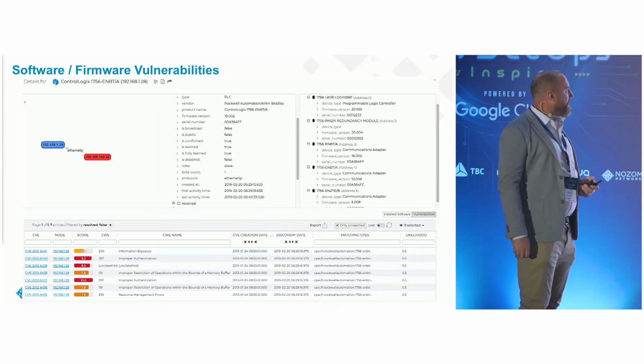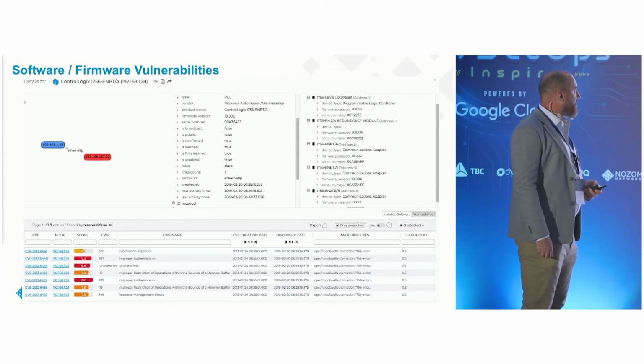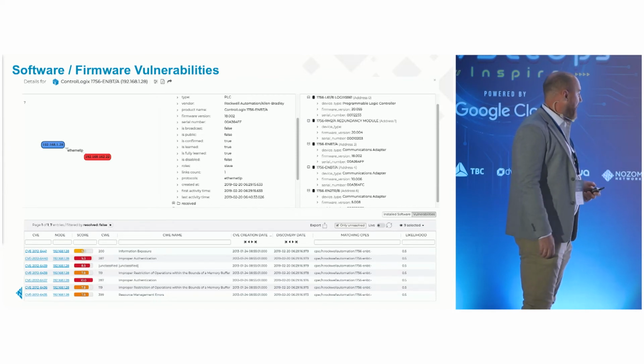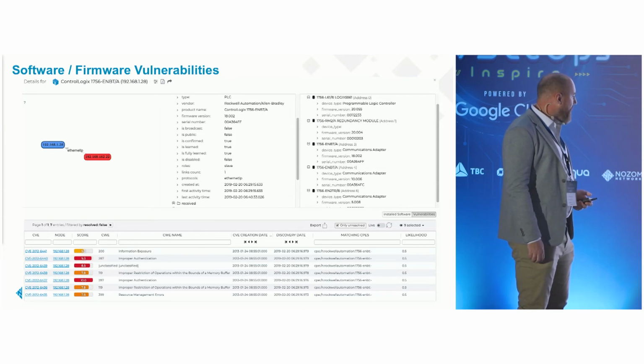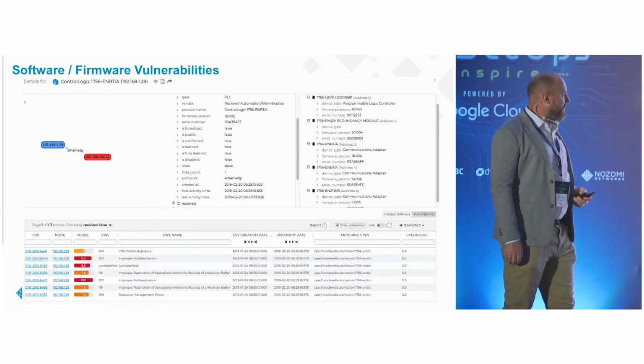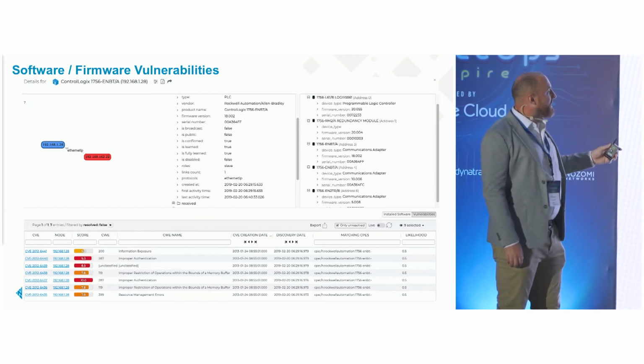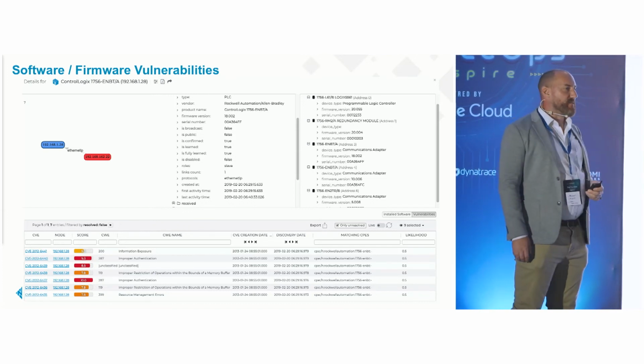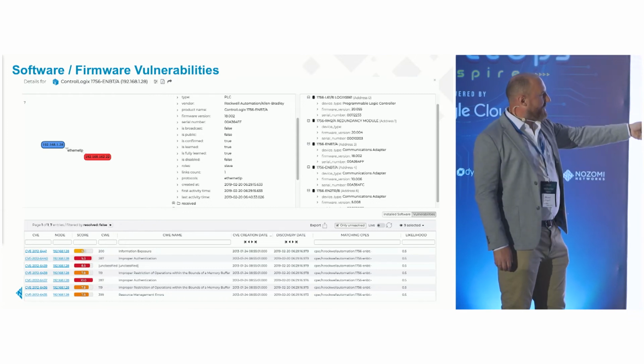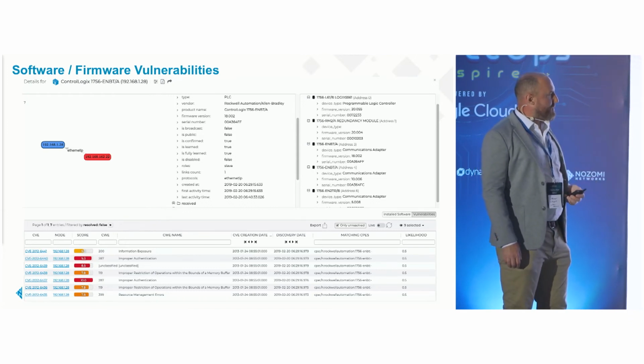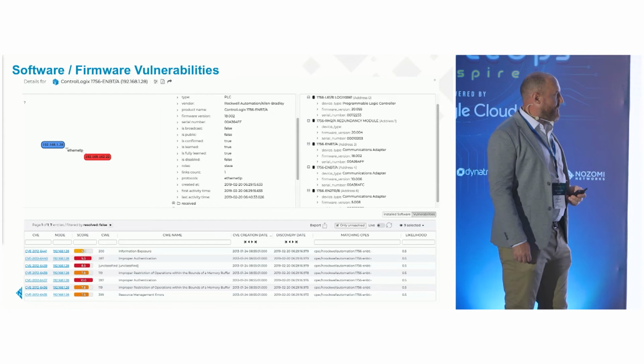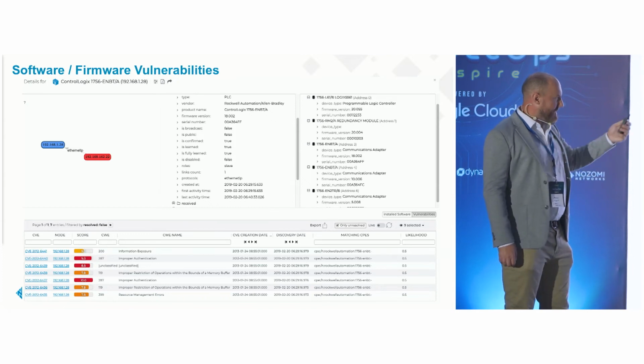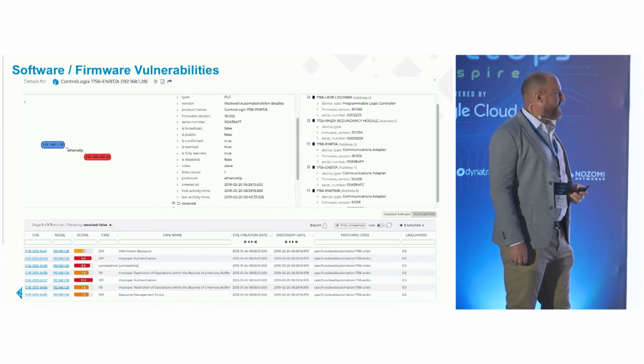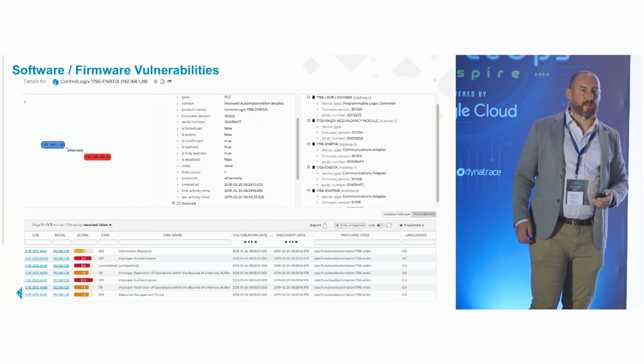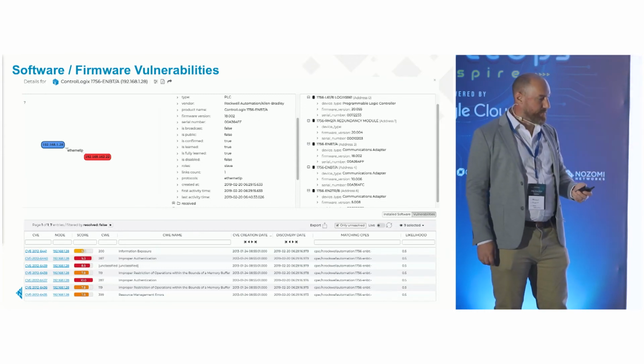Software and firmware vulnerabilities with the Rockwell ControlLogix PLC. Again, this is just a deeper look at it. We list out the vulnerabilities and the CVE score to have an understanding of what's potentially vulnerable. This is all passive detection of the device. We're able to pick up even the components plugged into the PLC, so we can see the firmware version and any vulnerabilities with the redundancy module, communications adapters, and all the little components that might be plugged in talking to the devices behind a PLC.